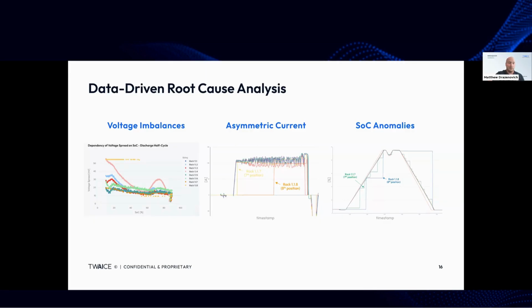A big one that's been coming up lately is just state of charge anomalies. In the plot on the right, we can see large jumps in SOC for some racks. While they ultimately start and end at the same point, these SOC anomalies can ripple through up to the EMS level system SOC, basically giving the EMS a wrong idea of where the system is actually at. And if you have racks turning off earlier than expected, it might take down all racks connected in parallel, things like this.